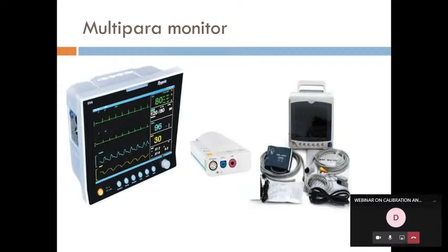Okay, this way you can check whether the machine is working or not. Then this is an ECG machine. How do you test the ECG machine? For example, if the doctor calls you and the machine is not showing the correct ECG value, there is an artifact in the machine. Then at that time you need to take a simulator, connect all the cables to the simulator, set a value and take a printed copy. If the machine is okay, then there is no issue with the machine. Okay, if not, you need to change the accessories.